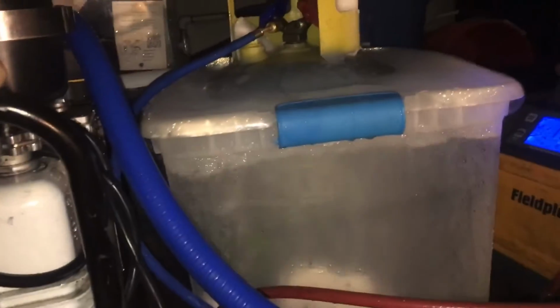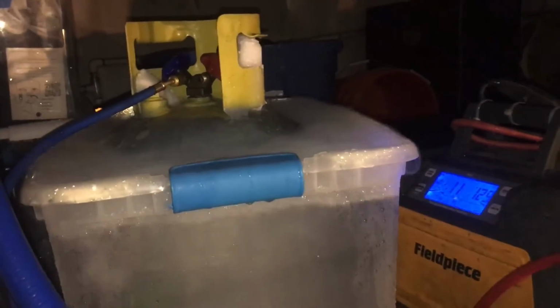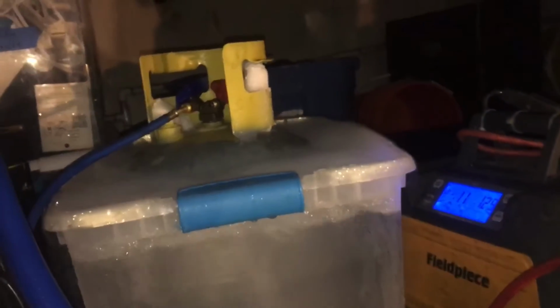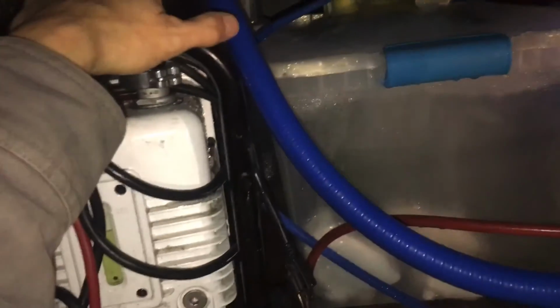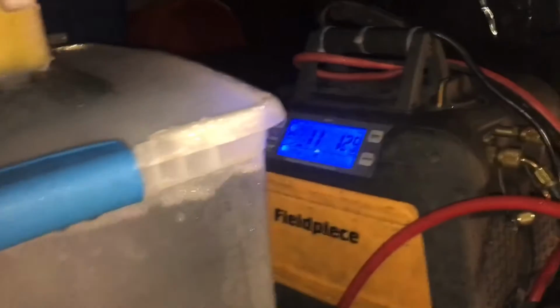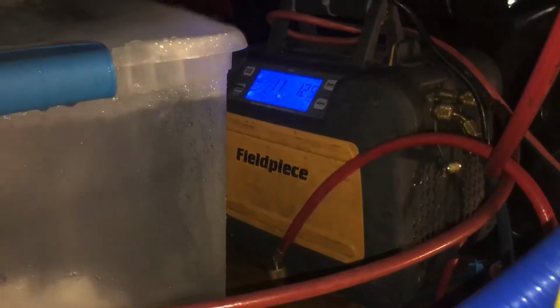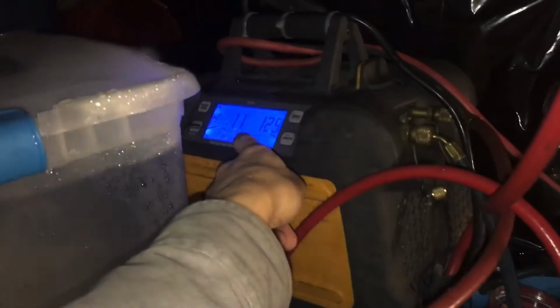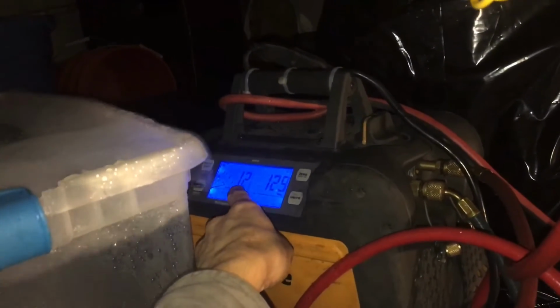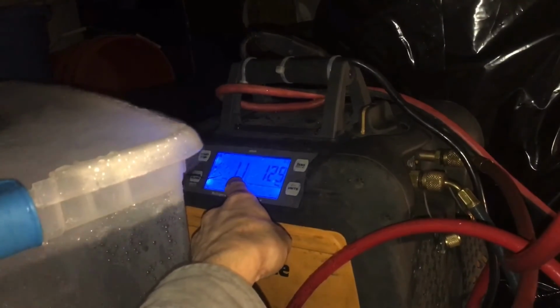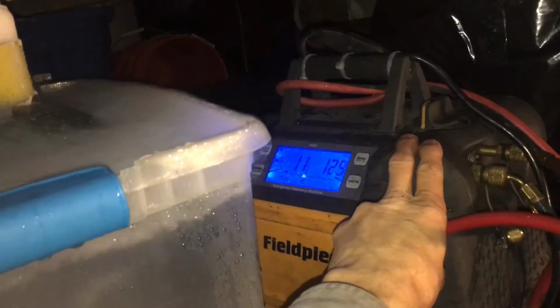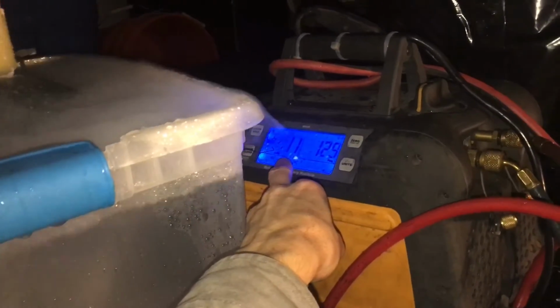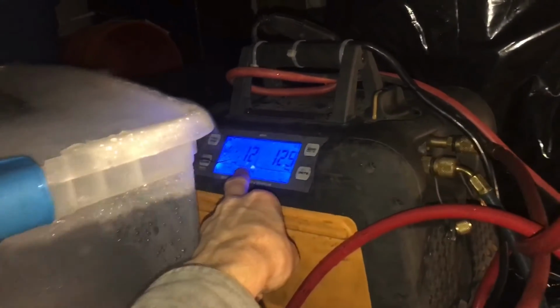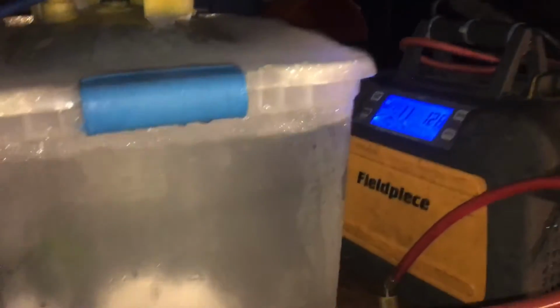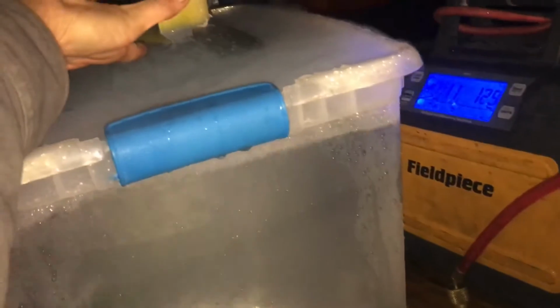And I'm trying to achieve well below 500 microns. If I could get it back to the 200 micron level, that would be really nice. But on a used system and gas in it on a cold day, even after 24 hours, that may be a little difficult. And when we came in here and we went to lunch, it was -10, negative vacuum, cooling down. Then we went to lunch, and we're coming back from lunch right now, and we only dropped the vacuum by 1 psi. That's how large the system is. And this is below 32 degrees.